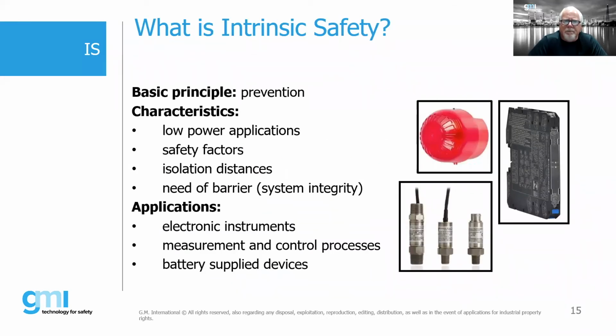So what is it? Again, it's prevention. The characteristics are low power applications. Generally speaking, when we're talking about intrinsic safety, we're talking about an effective amount of power of about 1 watt or less. We had a question in one of the last seminars about making motor starters suitable for IS, and unfortunately, you really just can't do that. Anytime we start getting into any higher power applications, we really just cannot use intrinsic safety. So it's really low power applications.